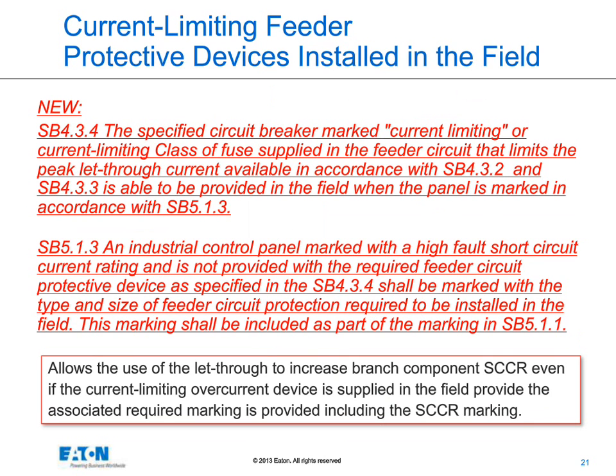A new change allows you to provide the overcurrent device in the field. So, for instance, if we had a fuse or current limiting breaker in the feeder, it could be provided by the customer in the field, provided the equipment is properly marked with what was required per SB 5.1.3. This allows the user — rather than the OEM — to provide the overcurrent device installed outside the equipment, and still maintain the high SCCR.